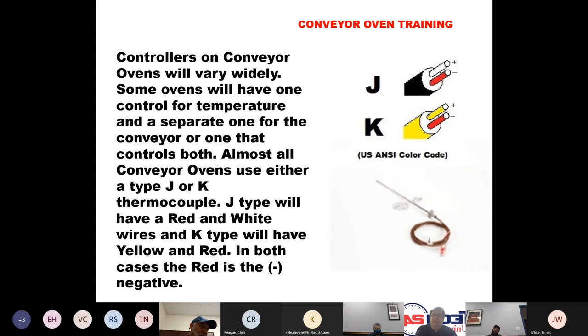So, sensing temperature. Controllers on conveyor ovens will vary widely. Some will have one control for temperature and a separate one for the conveyor, or one that controls both. So you may have two boards, one for the conveyor, one for the heat, or you may have one board that does both the conveyor control and the heat.